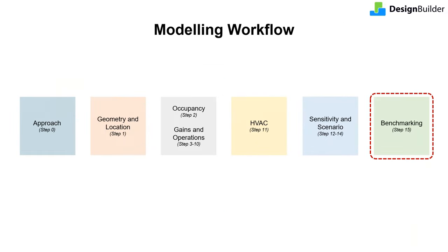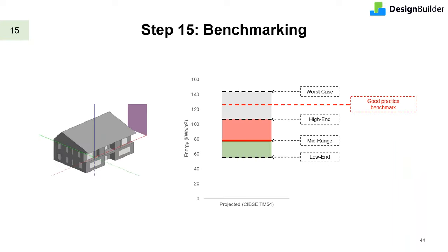The final part of TM54 is to compare the calculated performance against benchmarks of actual building data. This is a comparison of our demonstration model against the benchmark numbers given in CIBSE for good practice in this building type. The building design projection along with the high-end scenario is within the limit, so it's likely that the building — even if not operating as per design conditions — would still be better than the good practice benchmark.